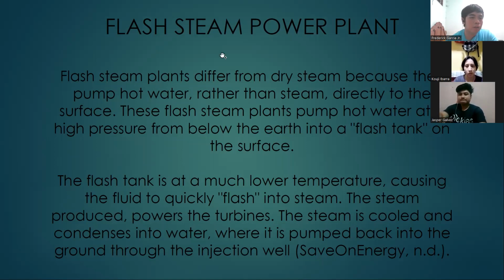The flash steam process is somewhat similar, but with an extra step. Rather than using steam directly, it uses superheated water that has not yet evaporated. The groundwater in these geothermal plants can be under a lot of pressure, meaning it doesn't vaporize into steam. But if you introduce it into a lower pressure area, like the flash tank, it instantly vaporizes into steam, or 'flashes,' as it's called here. That's what we use to power the turbines, and the process continues as before, pumping the condensed water back to the earth using an injection well.